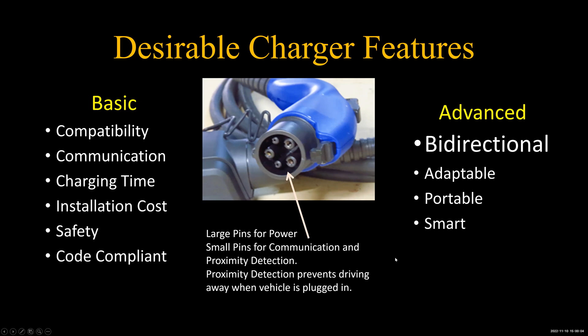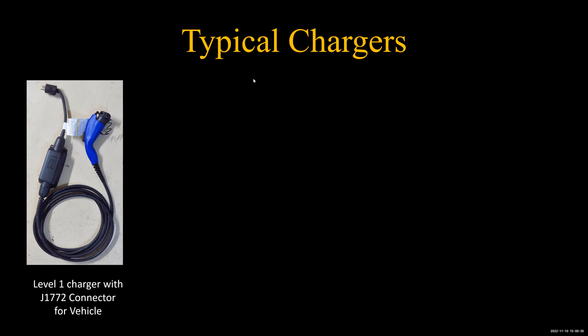So moving on, what's a typical charger look like? This is the simple level 1 charger, and you can see it has a standard 3-prong plug to plug into a 120-volt outlet. There's a few little holes so you can screw it up to your wall. You want to keep it 18 inches above the floor if you're in a garage. You need to do that for any electrical outlet, and otherwise the rules are pretty straightforward.